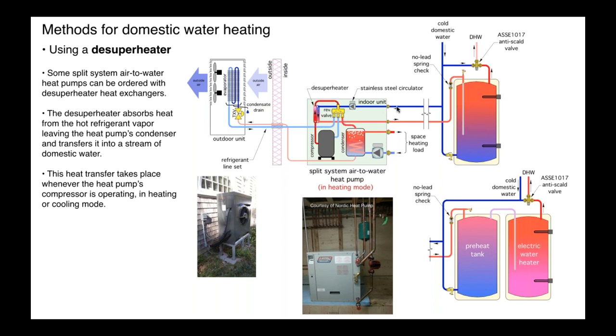And then the secondary side of the heat exchanger has water from the bottom of the thermal storage tank, let's say the electric water heater. That cooler water goes through a small stainless steel circulator, goes through the heat exchanger, gets heated, and then goes back into the dip tube in the water heater. So what we're doing here is we're scavenging heat from the refrigerant and putting it into the domestic water tank.